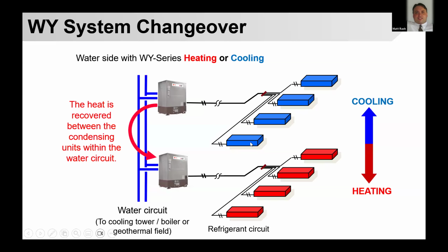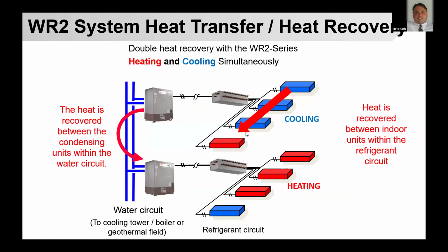Again, those are all fed with refrigerant, and there's changeover methods for when they all go to cool or all go to heat. We're not going to really talk about those details, but just know that is one limitation of these systems. They all have to change over together, but any excess heat absorption or rejection is shared on that condenser water loop. So taking things a little bit farther, as I mentioned, we have a heat recovery VRF system which allows individual zone fan coils to operate in different modes at a given time, and then also subsequently can reject or absorb heat and share heat across that common condenser water loop.